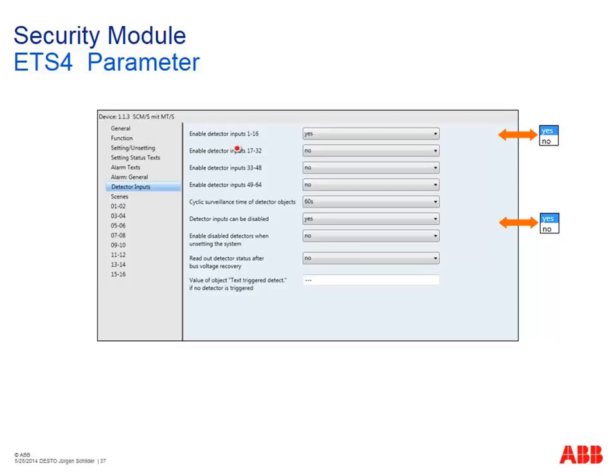In the zone parameters, up to 64 zones can be enabled in groups of 16. Cyclical monitoring of security terminal signals can be set — for example, every 60 seconds the terminal must send the input status. Zones can be disabled via a parameter or via a 1-bit group address — for example, disabling group 4 switches off all inputs assigned to that group so they make no alarm.